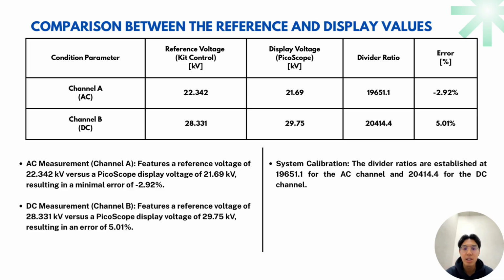To safely step down this high voltage for signal processing, the divider ratios were calibrated to 19651.1 for the AC channel and 20414.4 for the DC channel. In conclusion, both channels demonstrate strong alignment, while channel B approached a 5% variance. Both remain well within safe operational tolerance for high voltage testing equipment, validating our measurement setup.